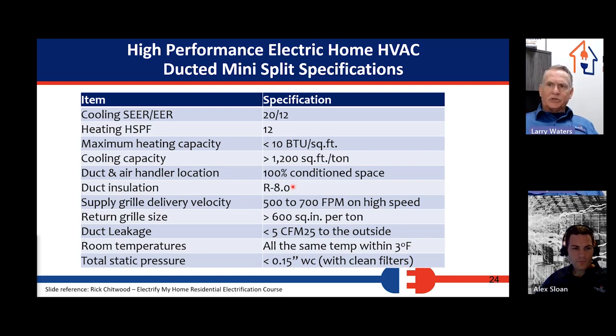So duct insulation should always be R8, buried in our case. Our duct leakage should be less than 5 CFM, all the temperatures in the room should be within 3 degrees, and we should not have more than 0.15 static pressure with clean filters. Now, these are high performance electrification specifications. These are not things you're going to be able to do in a typical home, but this is what we're looking at as the benchmark. So we can get somewhere in between what we're doing now and the benchmark and make a lot of improvements.